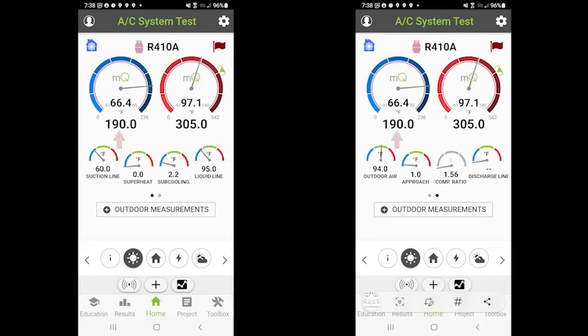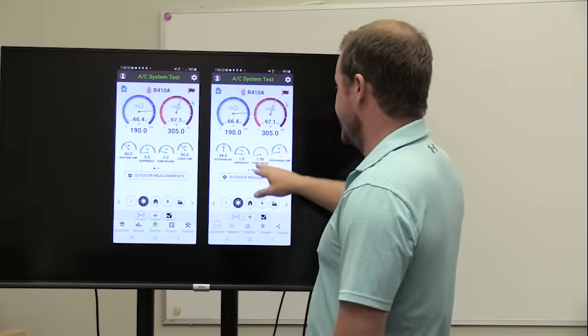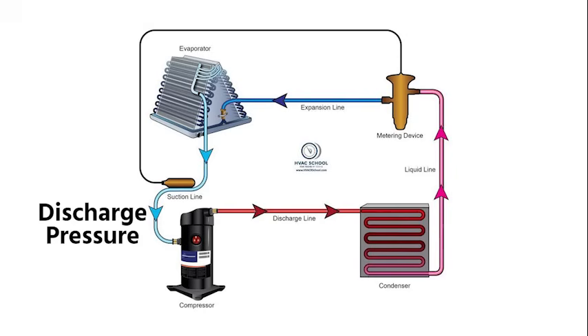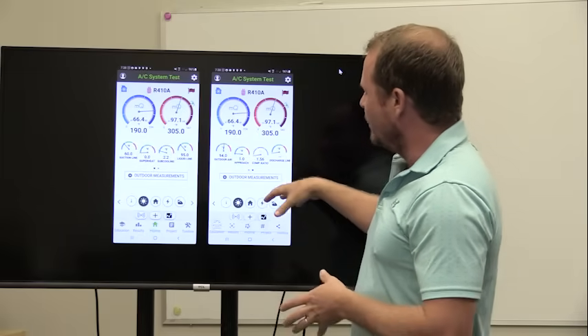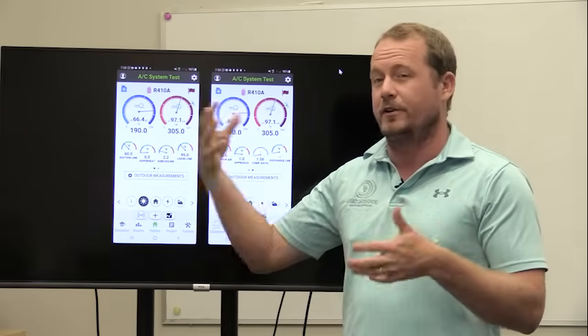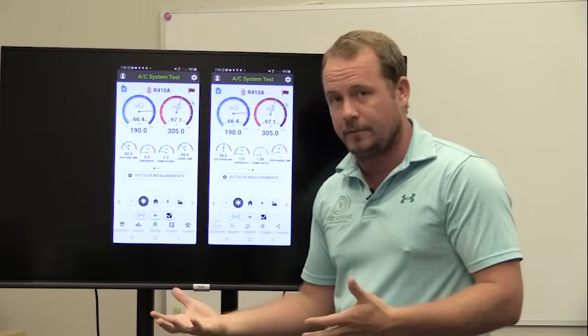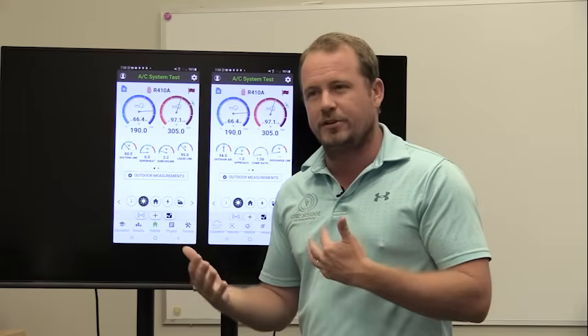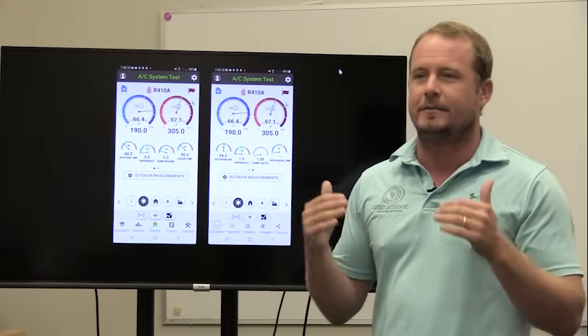So that's typically what you're going to see in those cases. You're going to see high suction, or high evaporator temperature, you're going to see low head, low condensing temperature, those mean the same thing. You're going to see a low compression ratio, which just kind of anchor what compression ratio is, it's just a fraction of your discharge pressure divided by your suction pressure right at the compressor. And this is where it also gets tricky, because in most cases, when we're doing this, we're not really going to get a true compression ratio, because we're not usually measuring discharge pressure, we're usually measuring liquid line pressure.